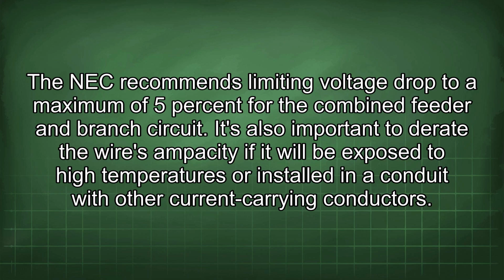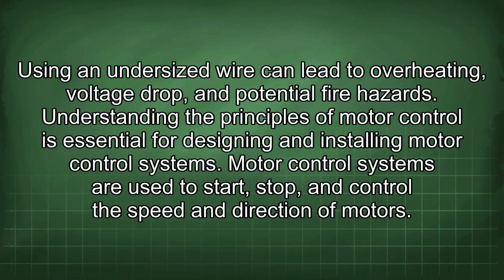It's also important to derate the wire's ampacity if it will be exposed to high temperatures or installed in a conduit with other current-carrying conductors. Using an undersized wire can lead to overheating, voltage drop, and potential fire hazards. Understanding the principles of motor control is essential for designing and installing motor control systems.